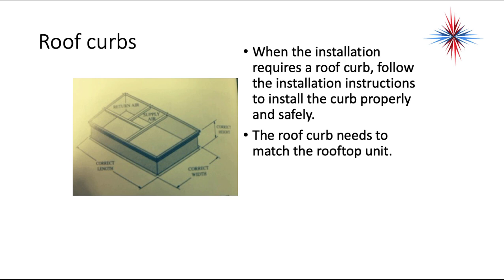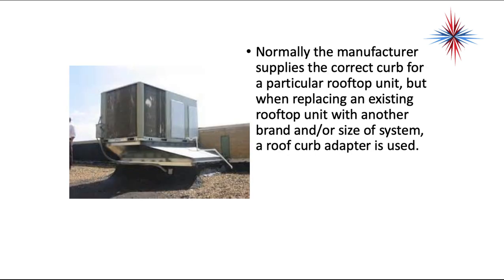When the installation requires a roof curb, follow the installation instructions and install the curb properly and safely. The roof curb needs to match the rooftop unit, and it's because of where the supply and return air are. It has to be the correct length, correct width, and correct height. Normally, the manufacturer supplies the correct curb for a particular rooftop unit, but when replacing an existing rooftop unit with another brand or size of equipment, an adapter is used. This adapter connects the old ductwork with the new ductwork.